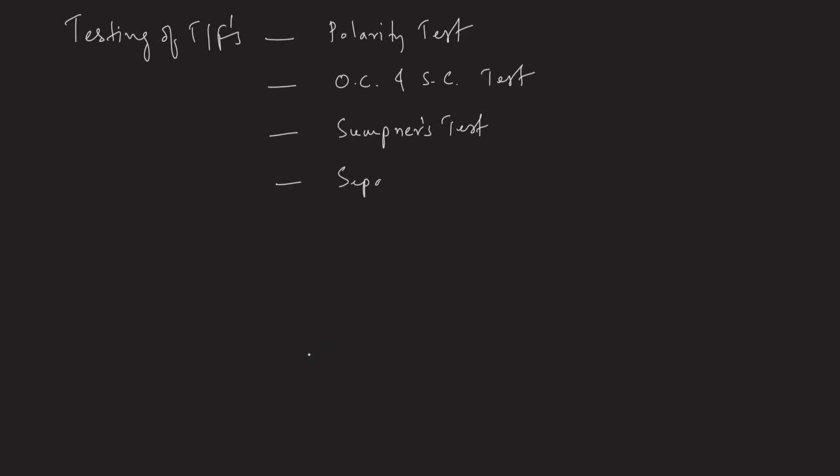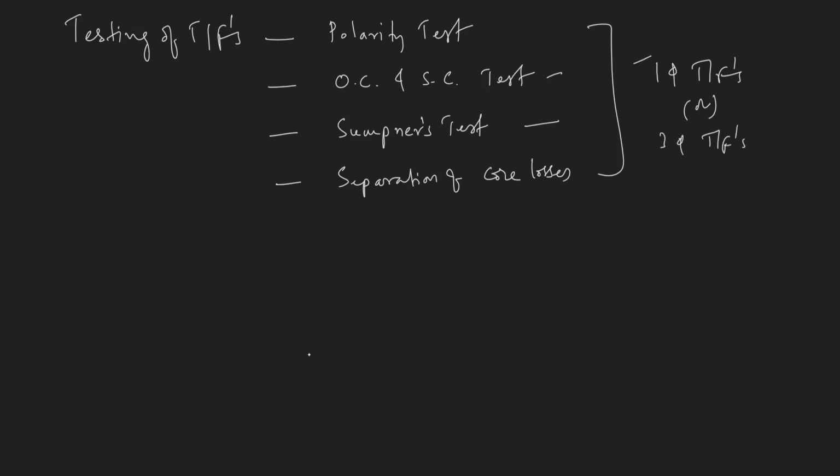First and foremost is the polarity test, then the OC and SC tests, short circuit test, one more is Sumpner's test, and the last one is separation of core losses. Sumpner's test and OC test can be carried out on single phase transformers or on three phase transformers, but for the time being I will explain for three phase transformers.